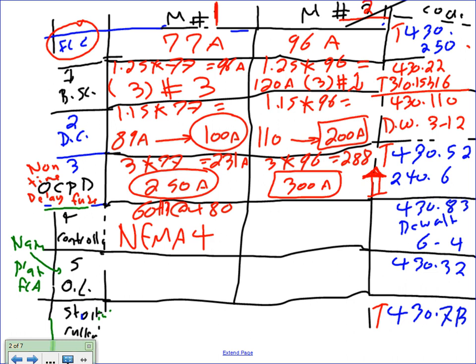And this one, a piece of cake: 75 horsepower at 480 volts. If you go there, it will get you the same thing, NEMA 4. Both of them are NEMA 4. Can anybody verify that it's NEMA 4? Everybody knows how to verify it from Table 6-4.